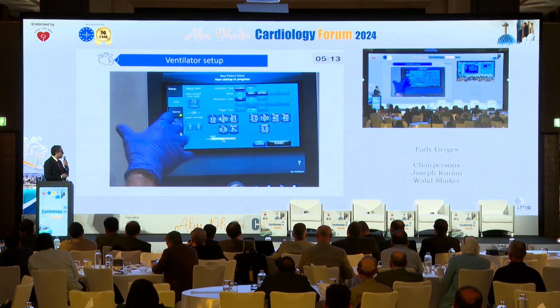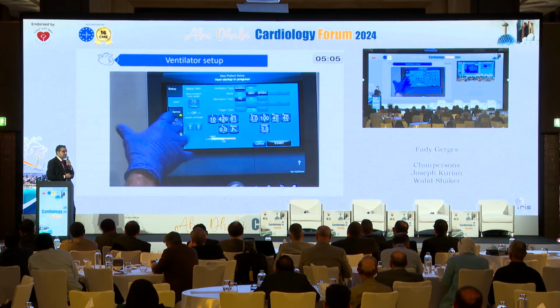It's all preset. Tidal volume is not a preset one. That means the patient determines it. So if you find this tidal volume below 300, that means there's something wrong. Then you have to add more pressure support, or you have to make sure there are no leaks.